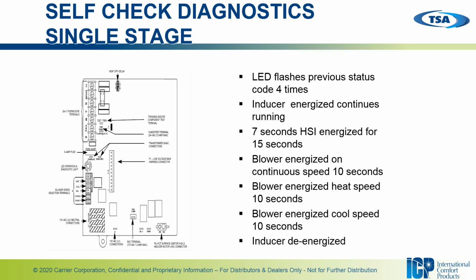And once you enter the self-check mode, the LED is going to flash the previous status code 4 times. And then your inducer will energize and continue to run. 7 seconds after that, the hot surface igniter is going to energize for 15 seconds, so be on the lookout to make sure your igniter is lighting. Once this takes place, your blower will energize on the continuous speed for 10 seconds.